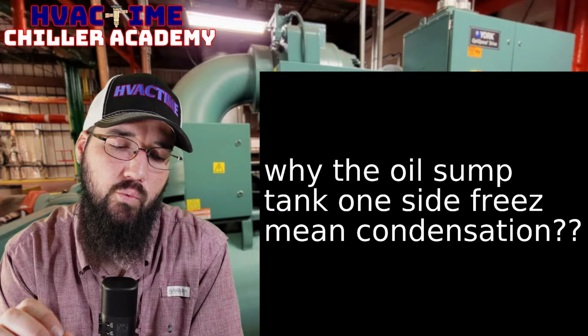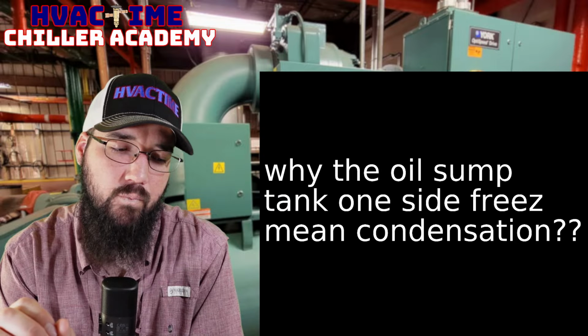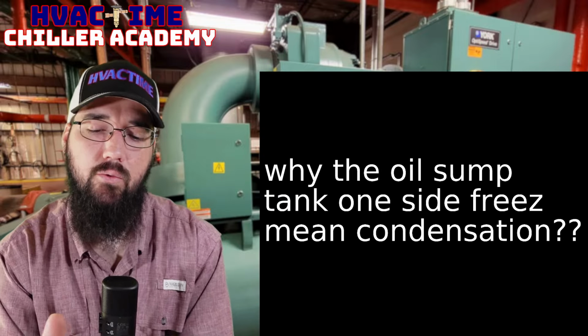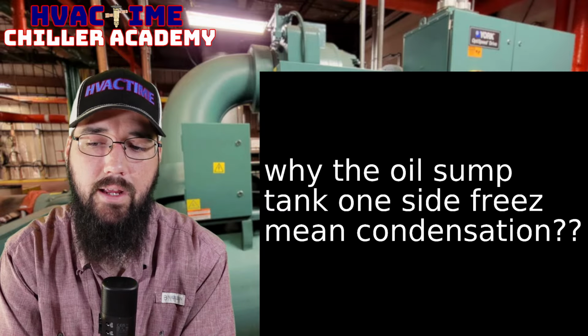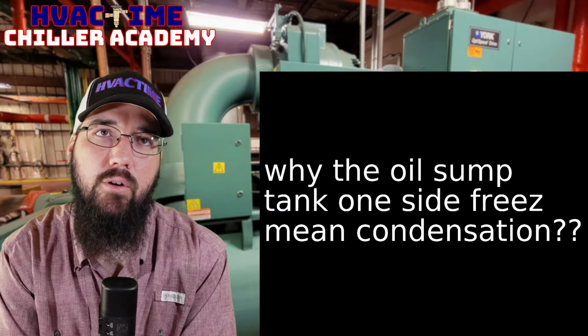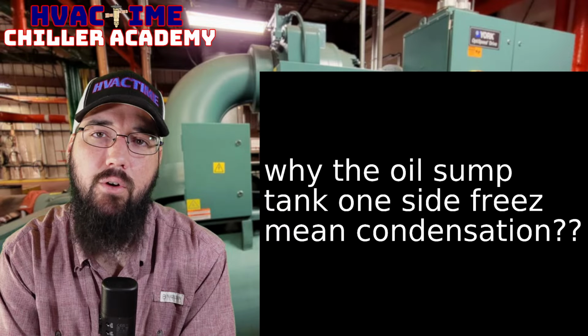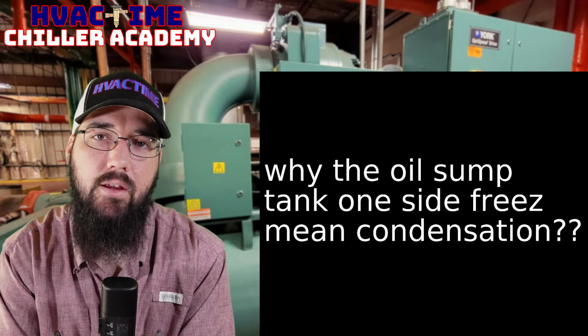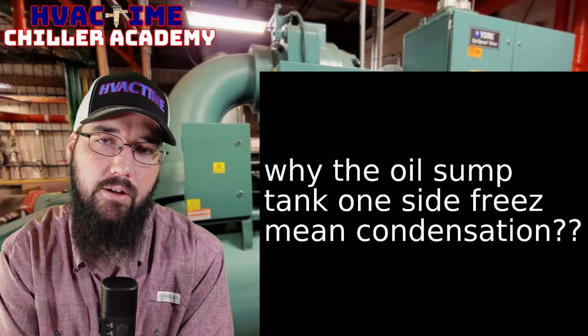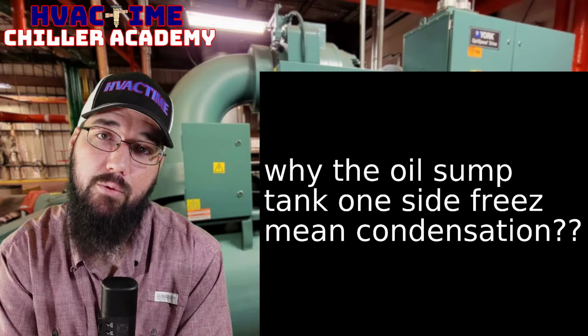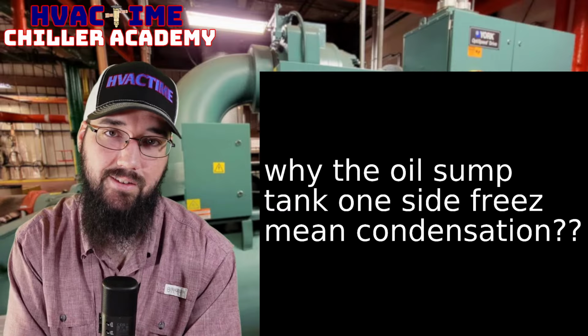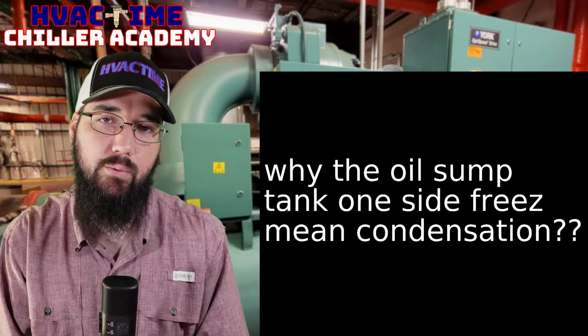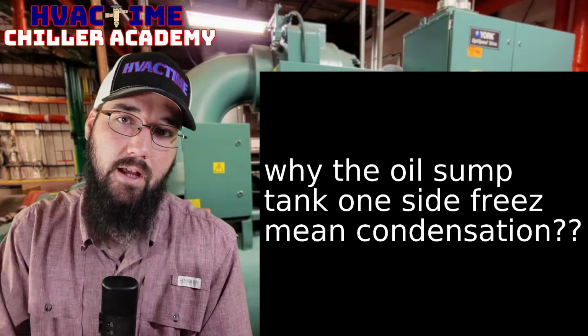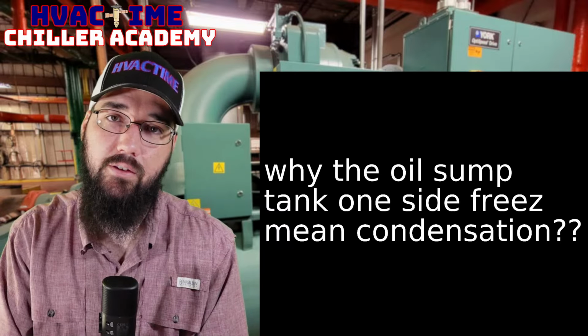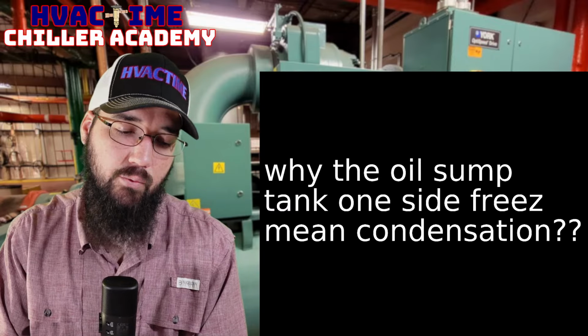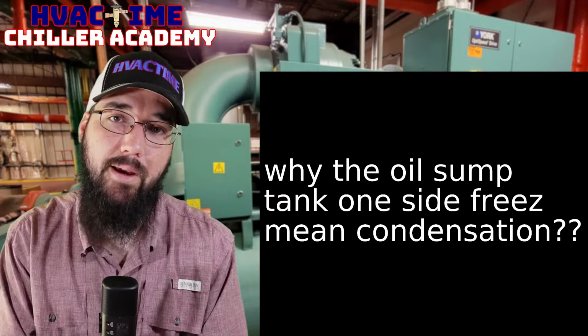So with sumps like this, I'll start off with using the YK example. If you're on a YK and you start running too high of a liquid level in the evaporator, you'll get up above the oil return line coming off the side of the evaporator, which, by the way, comes off on the inside between the two barrels on those YKs. That's where the eductor line is. That's also where you'll have your eductor filter, which is the filter dryer for the whole machine, and where your oil return solenoid and stuff is. All that's on the back side of the sump.